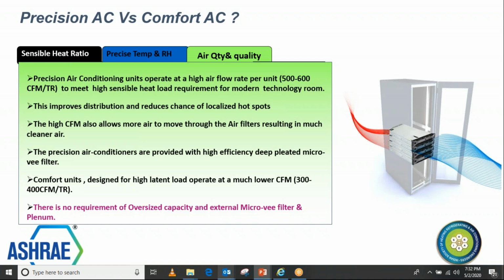So it's a big difference from the square feet to the watts ratio when you go from human cooling to the equipment's cooling. This is again an important point to note: when there are more watts per square feet, it's almost impossible to cool with just comfort air conditioners, because they are obviously not designed to handle this kind of heat transfer.